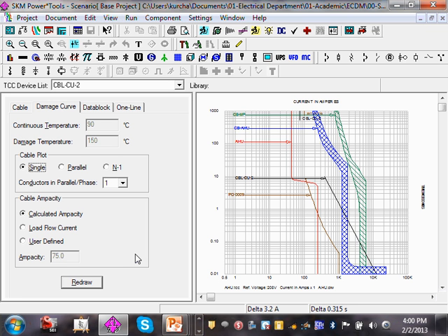Now what happens is, if you go down here for a short amount of time, you can carry, here's 1,000 amps, 2,000 amps, 3,000 amps, 4,000 amps, 5,000 amps, 10,000 amps. This conductor can carry 10,000 amps right here for how long? This is 0.01, this must be 0.02, so for 0.02 of a second. The same conductor can carry 10,000 amps for 0.02 of a second. That's called the damage curve of the conductor.